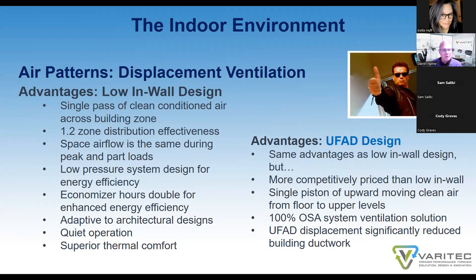These systems are a little more expensive because sheet metal needs to be brought down to each diffuser inlet in the wall. These systems allow for a single pass of clean conditioned air across the breathing zone, and offer a 1.2 zone distribution effectiveness rating. They provide the same space airflow during peak and part load conditions, so you don't adjust those flow rates. Low pressure system design for energy efficiency.